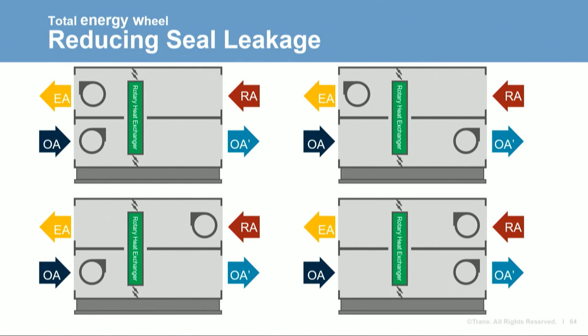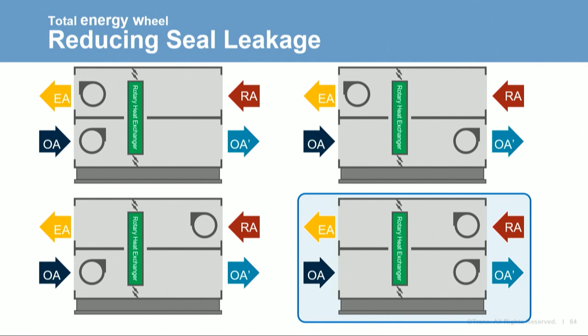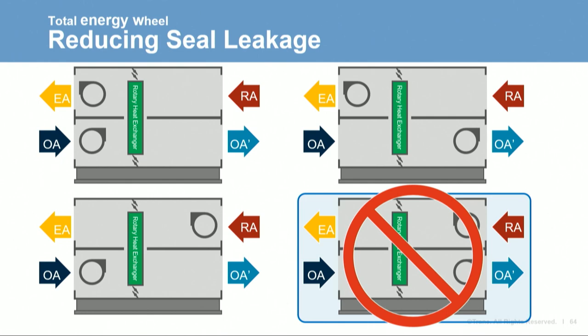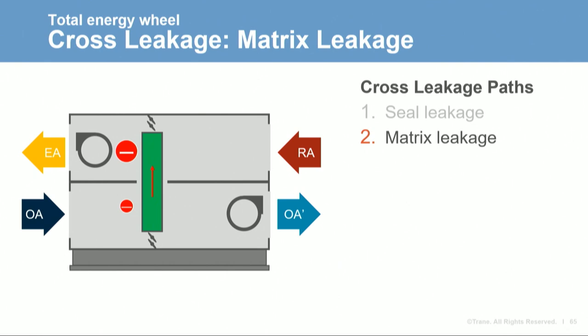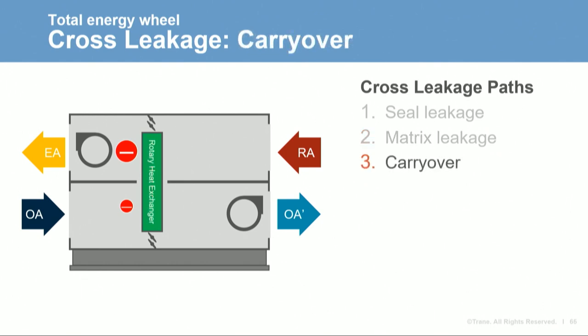The pressure differential between the exhaust and outdoor air paths should be minimized through careful fan placement. Various configurations exist — the fourth arrangement with a blow-through exhaust fan and draw-through supply fan will have the supply side as the lower pressure side, resulting in leakage from exhaust to supply, which is usually undesirable and not recommended. The wheel matrix can be manufactured in different ways; some designs allow air to migrate through the wheel causing matrix leakage. A third source is carryover, where air is entrained in the wheel as it rotates into the other airstream. A purge section can be added to flush the wheel with supply air to reduce carryover.